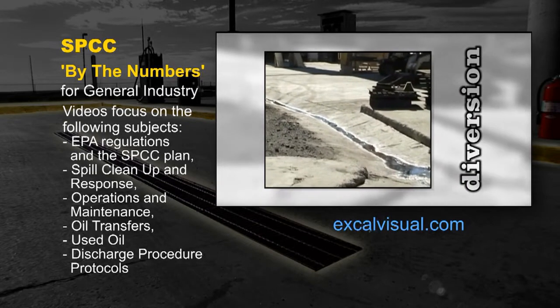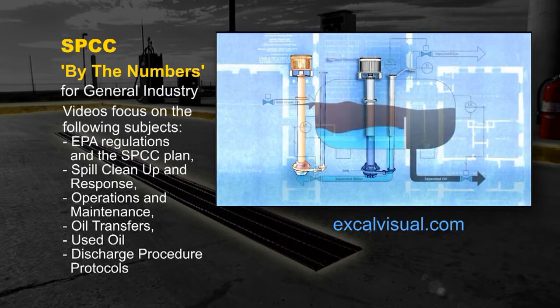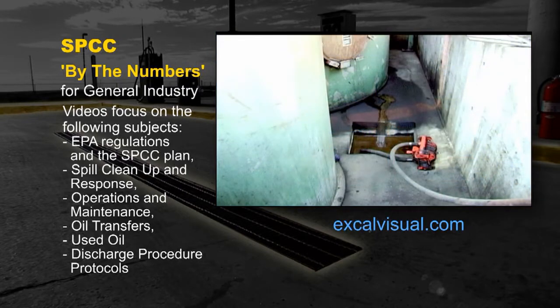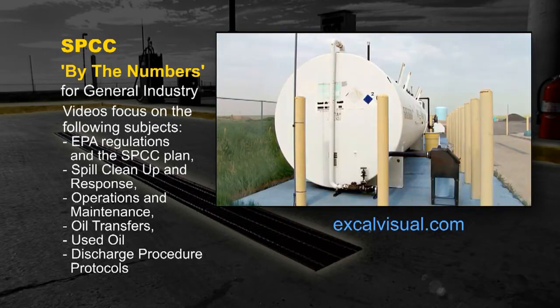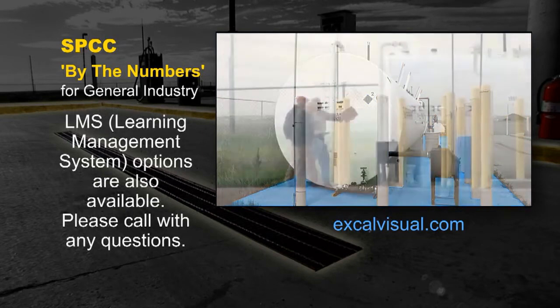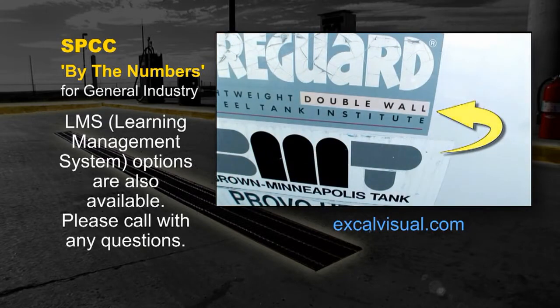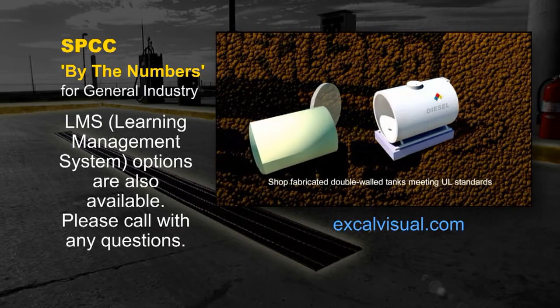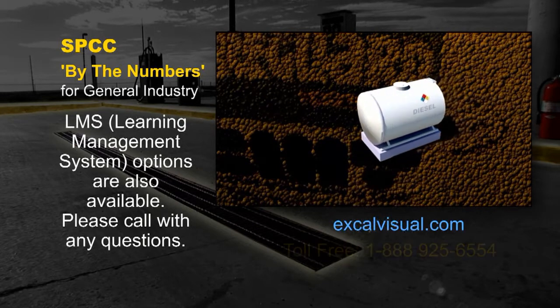Diversion is another method of spill containment. Sump pumps and oil water separators are sometimes incorporated into containment systems as well. These tanks appear to be without any method of secondary control. But closer examination shows these are double-walled tanks, a tank within a tank. Manufactured to very exacting standards, these tanks are a good way to prevent discharges and have the extra advantage of being very compact.